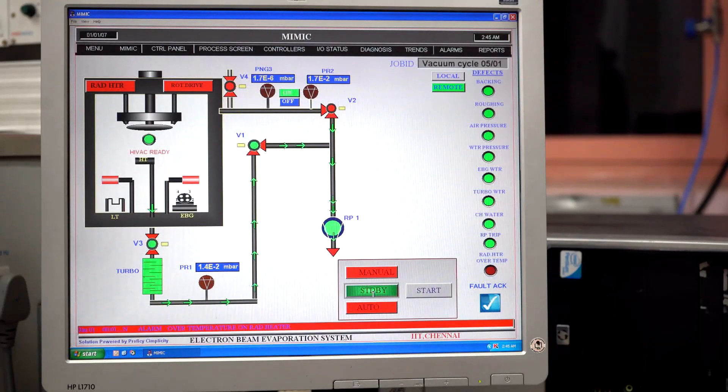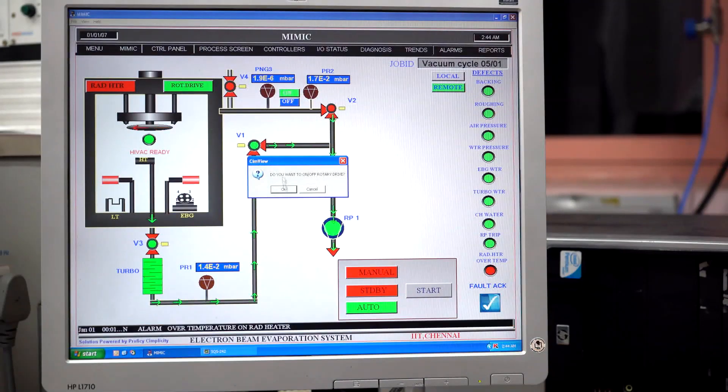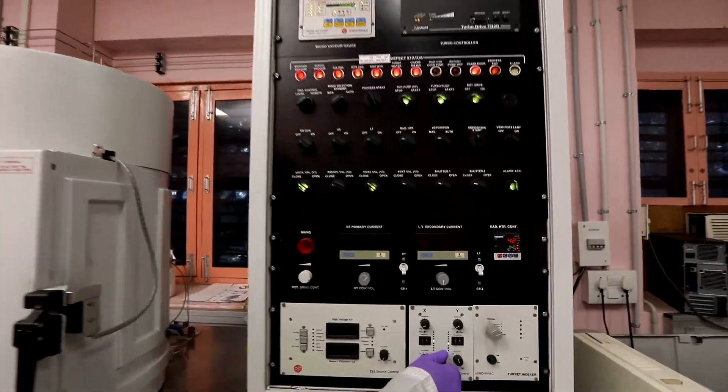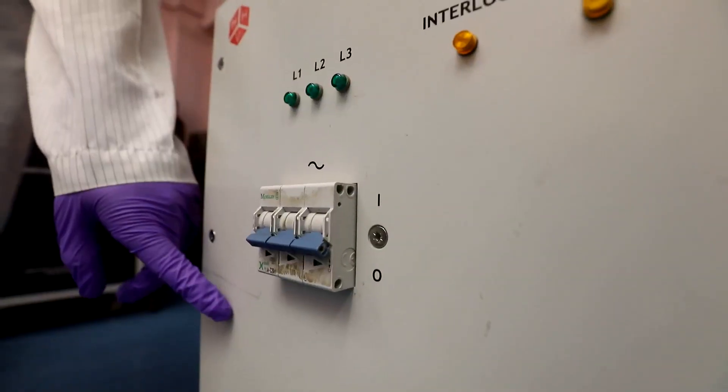Now switch off the sweep control, rotation drive, electron gun and pressure gauge. Wait for the temperature to ramp down to room temperature.